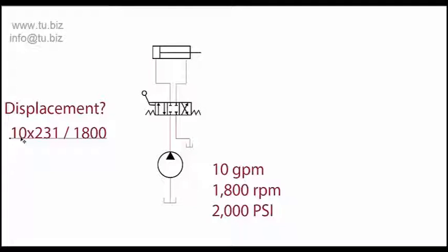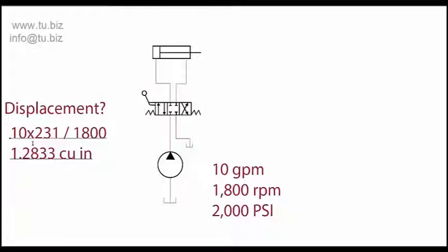I'll punch in the numbers: 10 times 231, divided by 1800, and it gives you a displacement of 1.2833 cubic inches per revolution. So now we have to go and select a pump for this application — now we have the size.